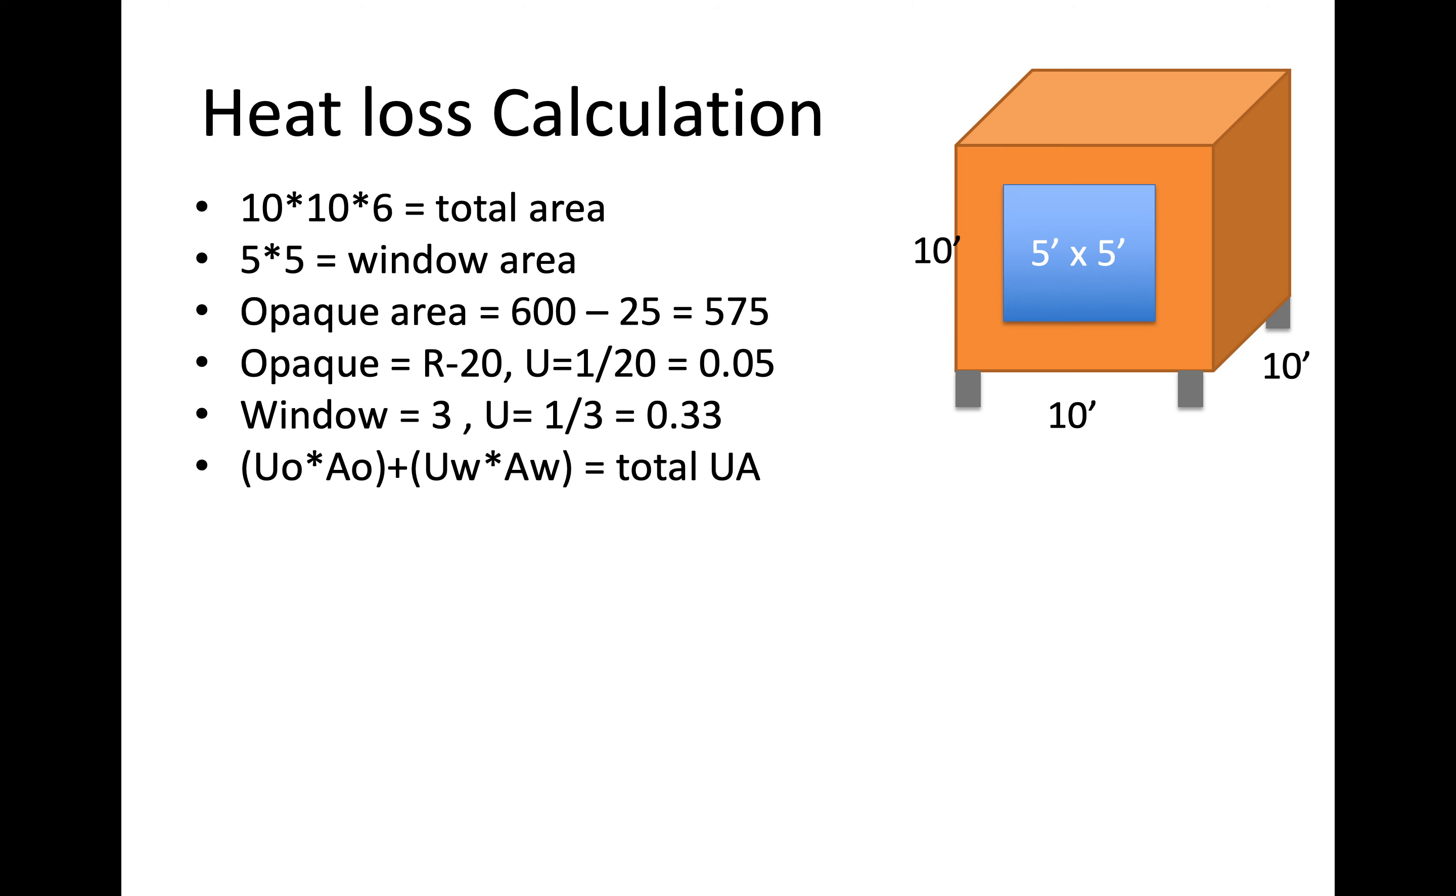So we're going to do an area weighted calculation. First we take the u factor for the opaque area times the area of the opaque area plus the u factor for the window area times the area for the window area and that's going to get us our total u factor times area. So if we plug those in, we can see that our total UA is 37.